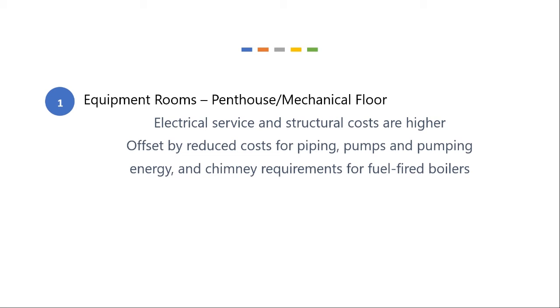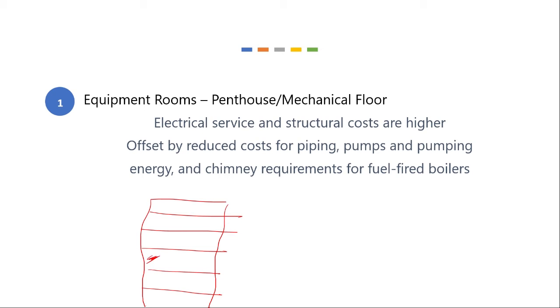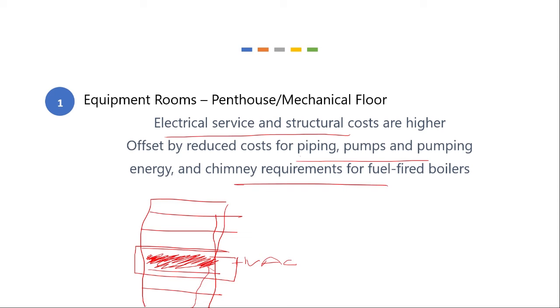Now, in large buildings, we have 3 floors or 10 floors or 40 floors. We can put our mechanical floor on one of those floors. So some office buildings, for example, say a 4th floor, this floor doesn't exist. And this floor has a secret elevator, and the only thing on this floor is HVAC equipment. And so we don't rent this floor out. And this connects to all the other floors via shaft. And it costs us a lot more electricity-wise and structure-wise because we've taken up one whole floor of the building for our equipment, but it's a lot cheaper as far as piping, pumps, energy, and chimney requirements.